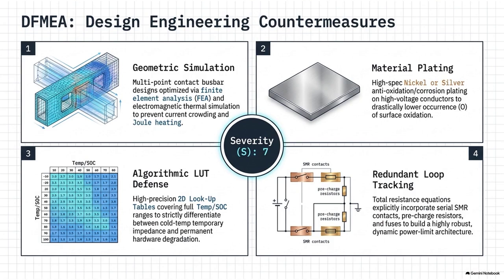To combat this, advanced DFMEA requires engineered multi-point or micro-bump contact designs. Wait, so they intentionally machine microscopic bumps into the surface of the copper? Yes. Engineers use finite element analysis, FEA, and coupled electrothermal electromagnetic simulations to model the exact geometry of the joint. They design specific, highly uniform microbumps across the surface. Why bumps? When the bolt applies clamping force, these engineered bumps are designed to plastically deform at very predictable rates. They flatten out to guarantee a massive, evenly distributed matrix of true contact area. They squish perfectly to make a solid connection. Yes, and the FEA simulations push virtual thousands of amps through these computer models to ensure the current density vector field is perfectly uniform, which entirely eliminates localized constriction resistance hotspots.